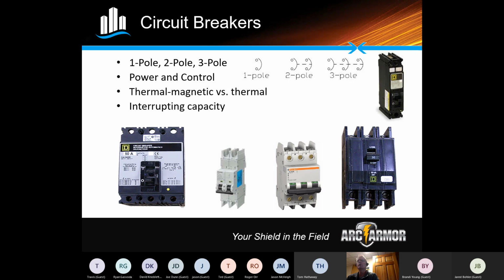My example is you have this breaker, you have a motor starter, and let's say the normal SCCR of that panel is going to be determined by the available fault current from the utility, right? So whoever is providing power to that panel will be able to tell you what the interrupt rating should be, or what the fault current available for that panel should be at that particular location. Typically, 5,000 is pretty low end, but it's pretty typical for standard 120 control panels. But you can also get into 42K, 65K, depending on what's there.